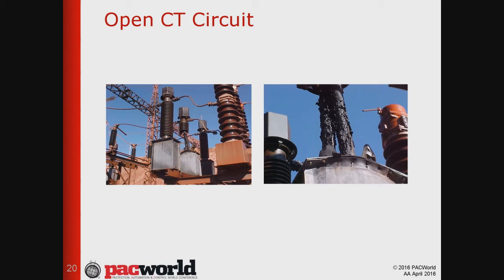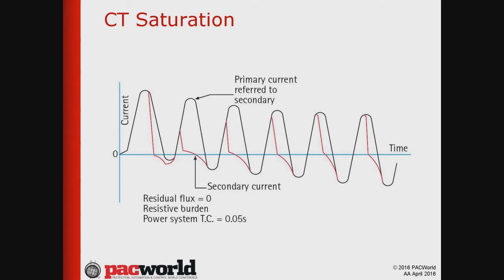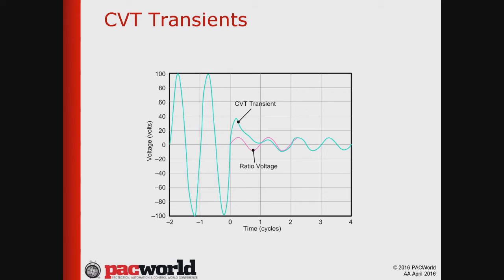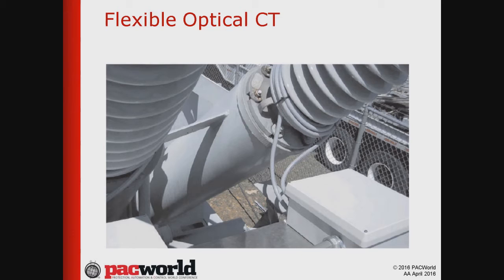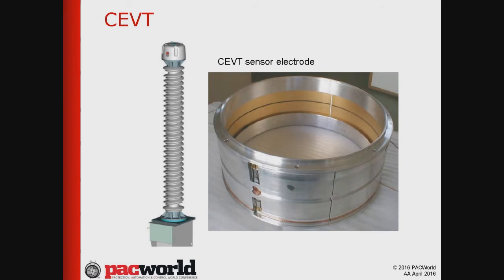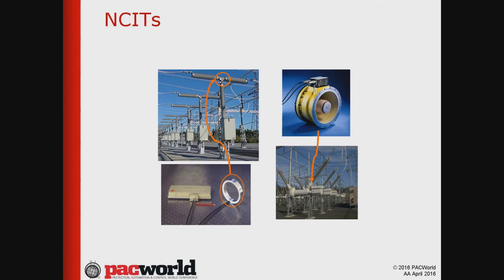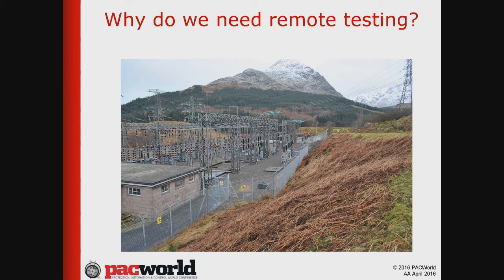One of them is failure of CTs. Failure of CTs has two different impacts. One is CT saturation, which is a traditional problem with CTs. The other is CVT transients, which is a problem with the voltage transformers. And how do we solve these problems? We use non-conventional instrument transformers that are coming from different suppliers, from Alstom, ABB, etc., in order to improve safety and eliminate these transient problems with the instrument transformers.